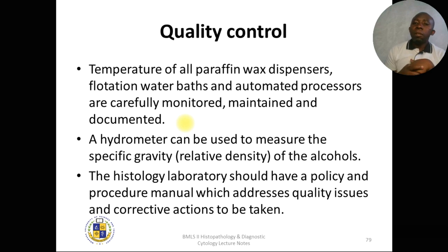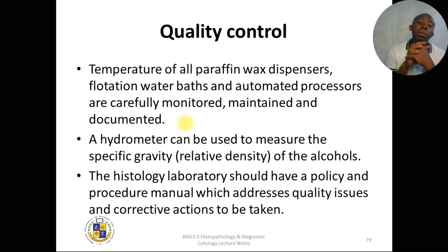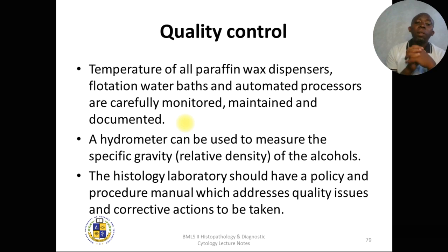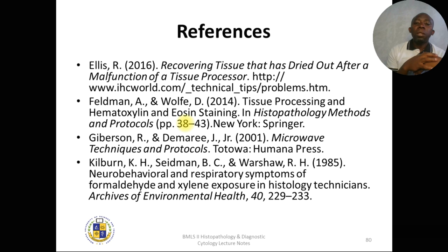For quality control: temperature of all paraffin wax dispensers, flotation baths, and automated processors must be monitored, maintained, and documented. A hydrometer can be used to measure the specific gravity of alcohol to ensure appropriate density for effective dehydration. The laboratory should have a policy and procedure manual that addresses quality issues and specifies corrective actions to be taken.